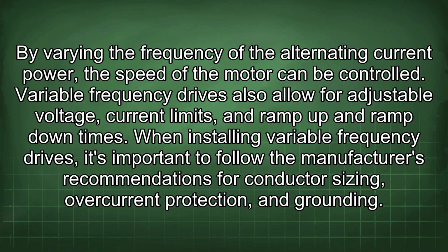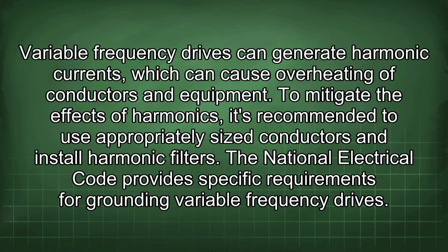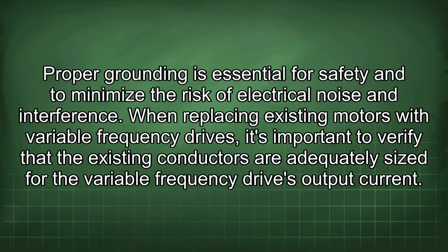When installing variable frequency drives, it's important to follow the manufacturer's recommendations for conductor sizing, overcurrent protection, and grounding. Variable frequency drives can generate harmonic currents, which can cause overheating of conductors and equipment. To mitigate the effects of harmonics, it's recommended to use appropriately sized conductors and install harmonic filters. The National Electrical Code provides specific requirements for grounding variable frequency drives. Proper grounding is essential for safety and to minimize the risk of electrical noise and interference.